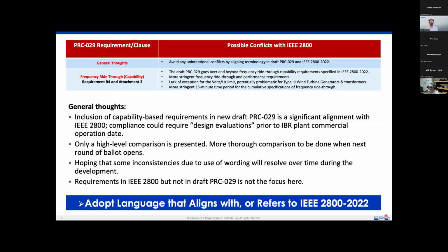But here are some possible conflicts that we would like to highlight. One is that there may be unintentional conflicts through misalignment of terminology in draft PRC 29 and 2800. Probably the most prominent one is that the draft PRC 29 goes over and beyond the frequency ride-through capability requirements as they are specified in IEEE 2800. The draft PRC has more stringent frequency ride-through requirements, aligned with what appears to be specific regions' requirements, which have not found consensus in IEEE 2800 as technical minimum requirements.